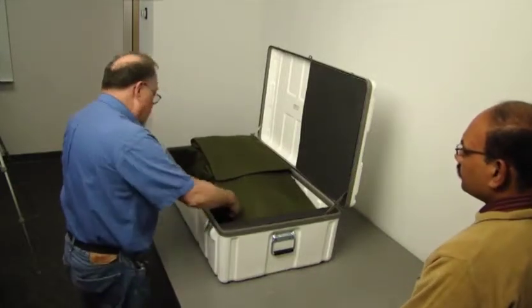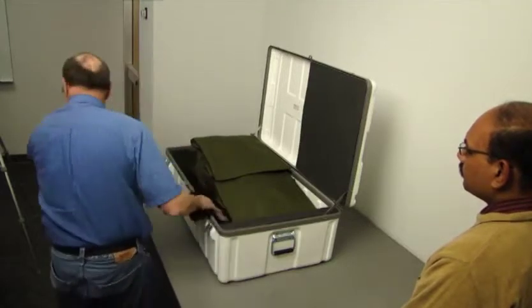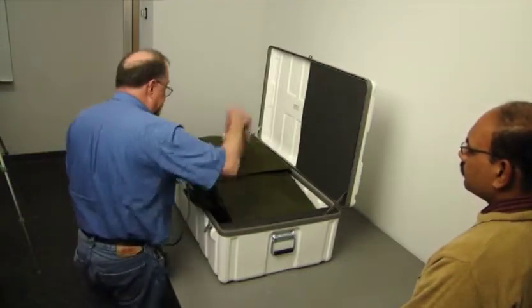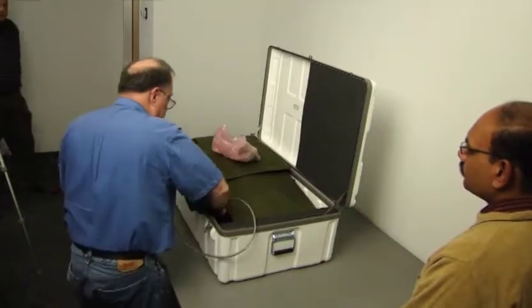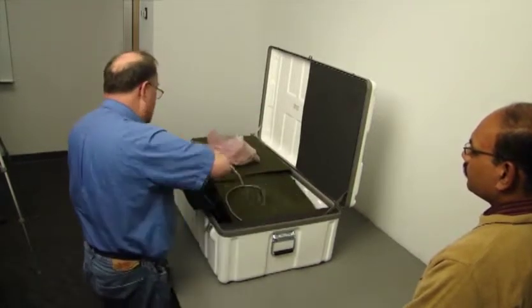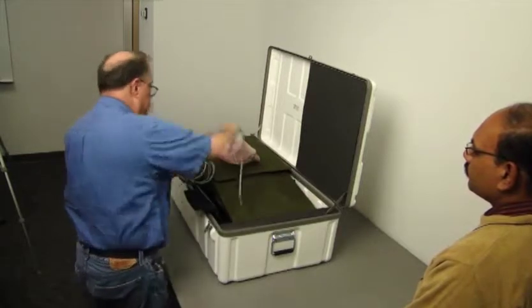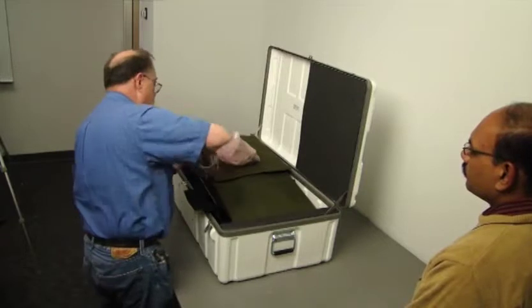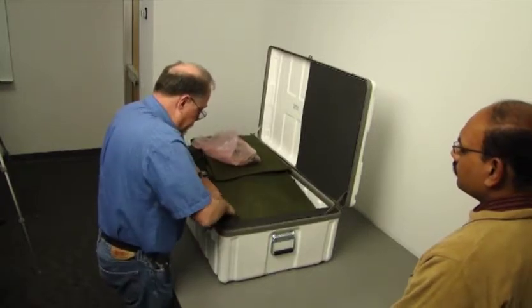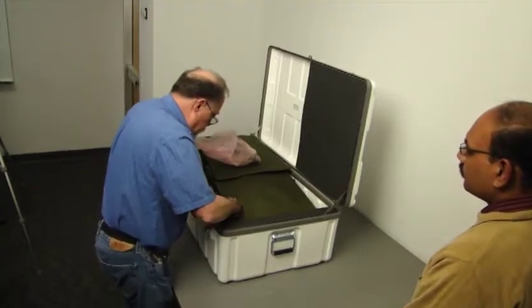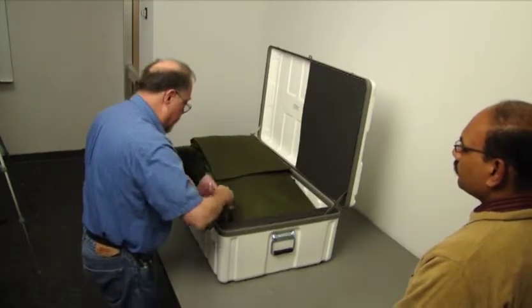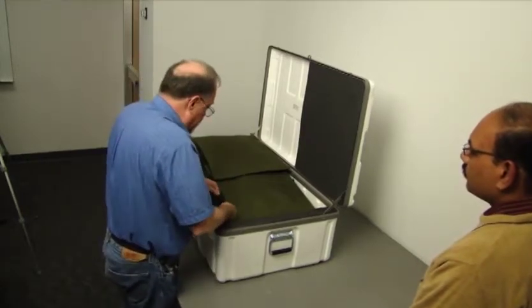The right hand case or pocket holds the sensor. If there are any cables in that case, temporarily remove them. Put the sensor down in the case and coil the sensor cable, being taken care of not to kink the cable. You have to coil it fairly tightly and fit the cable without kinks into the case. Make sure that nothing is pinched, nothing is kinked. And then there should be a little bit of room to fit any other cables that came out of that case. Finally close the Velcro strap.